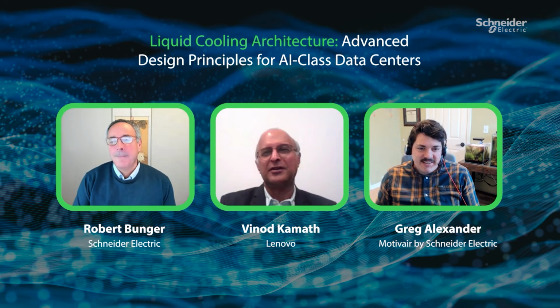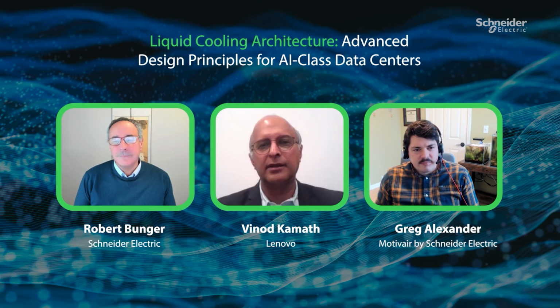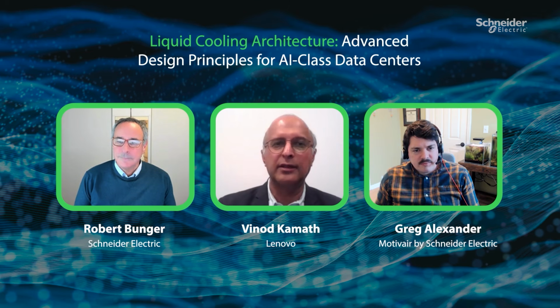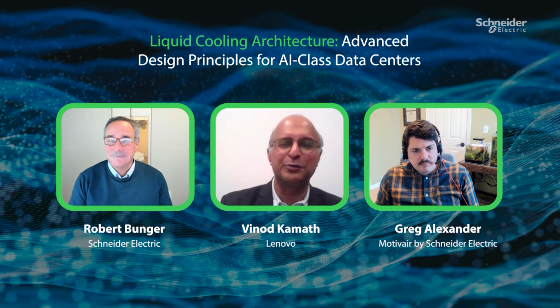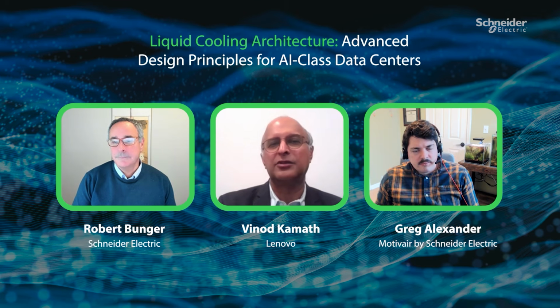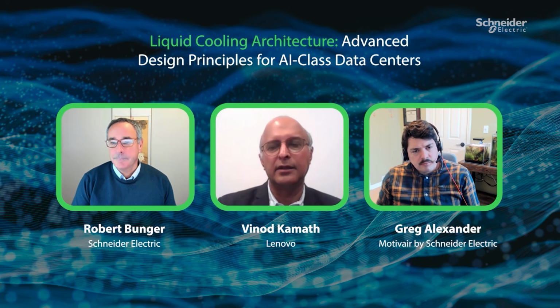Jokes aside, when we started liquid cooling it was an energy efficiency story. In Munich, the customer also had an expectation of minimizing water consumption, so they had a dry cooler on the roof. The dry cooler has an expectation of operation temperature, and even in Munich it does get warm in August. We designed our platforms for W45 back in the day, and now we have a TCS at 45. That W45 is difficult to maintain, so we have a W40 based cooling solution that we've deployed in a whole bunch of our customer environments around the planet.